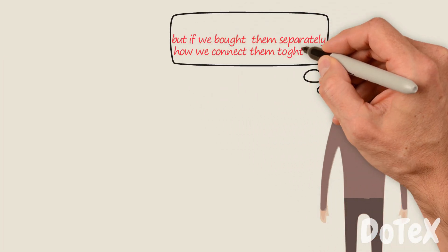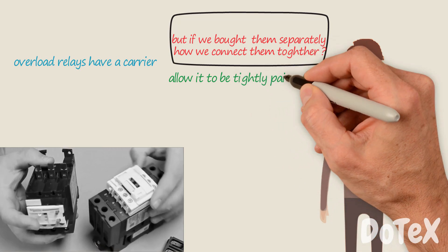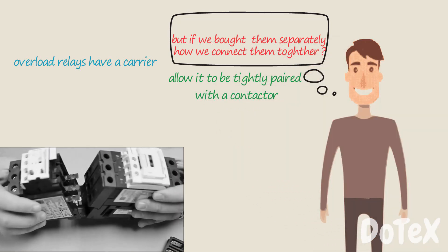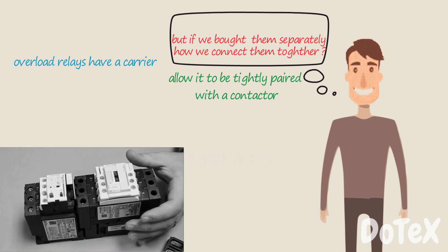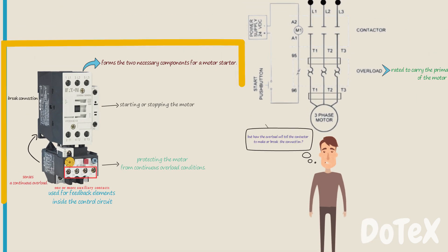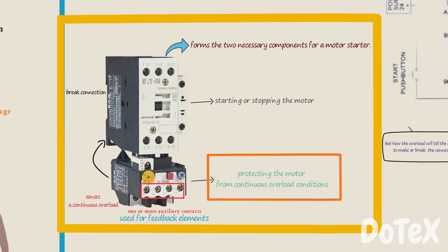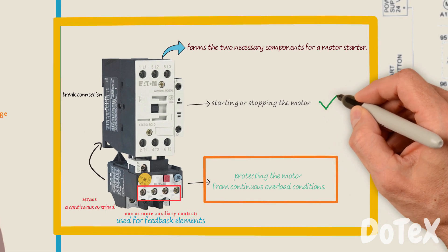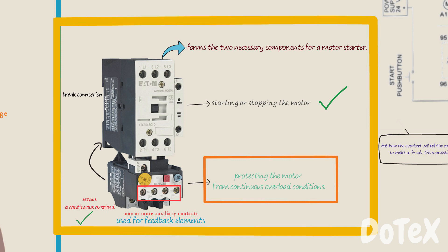But if we bought them separately, how do we connect them together? An overload relay by itself can't rightly be considered a motor starter, since it can't establish or interrupt the high current delivered to a motor — that is provided by the contactor. The overload's only purpose is to protect the motor from continuous overload conditions. This is why a motor starter is formed of two elements, so they can both make and break connection and detect continuous overload conditions. That's it for this video. We will continue the overload topic in the next video.